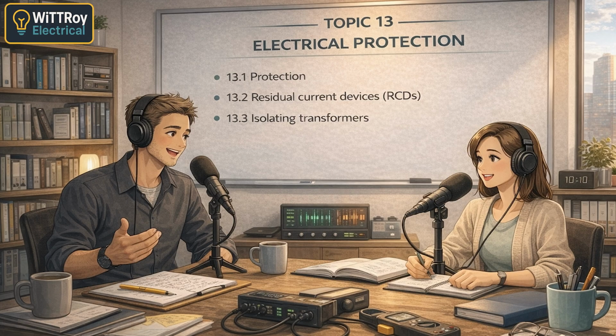Very important. Now, one more examinable term, breaking capacity. That's the maximum fault current the device can interrupt. Correct. So if the fault current is higher than the breaking capacity, the device can fail. Yes, and that's a serious safety risk. So breaking capacity must suit the prospective fault current. Exactly. Okay, that's a lot clearer now.